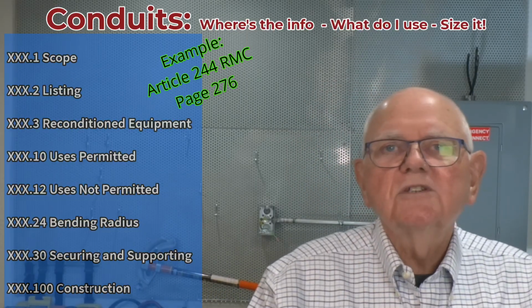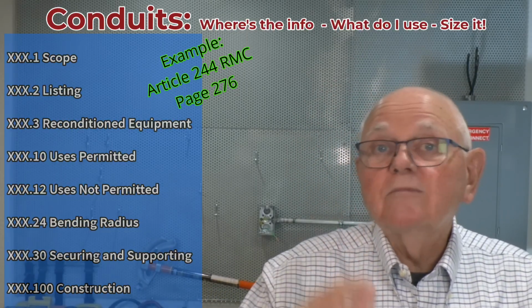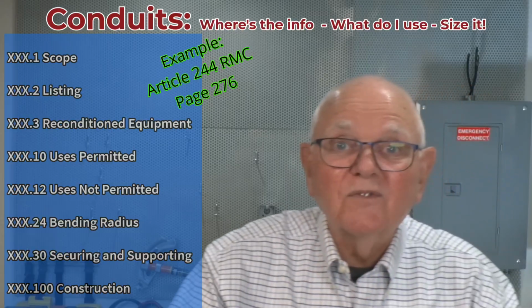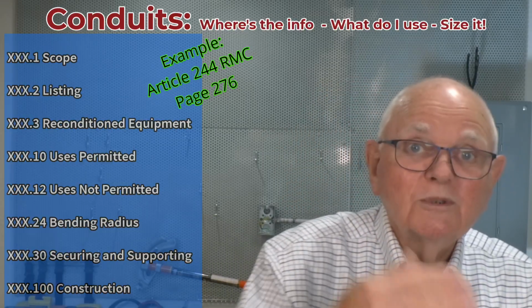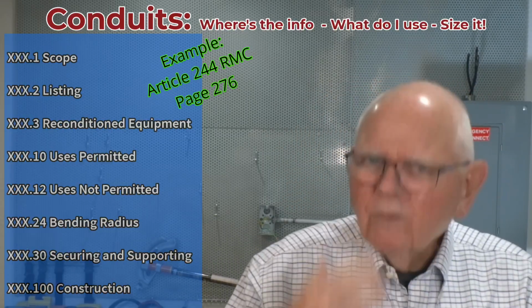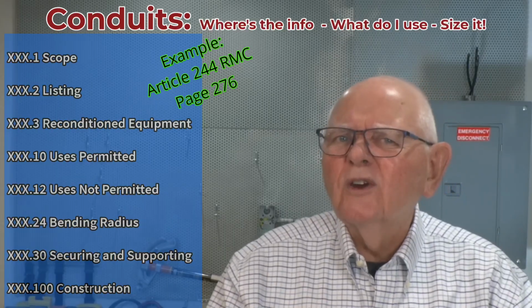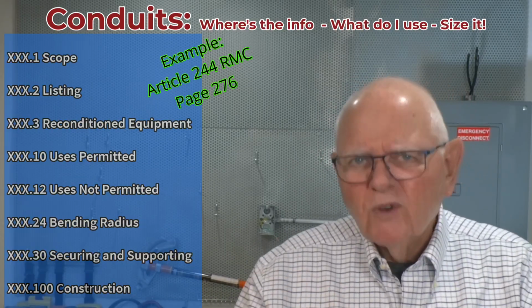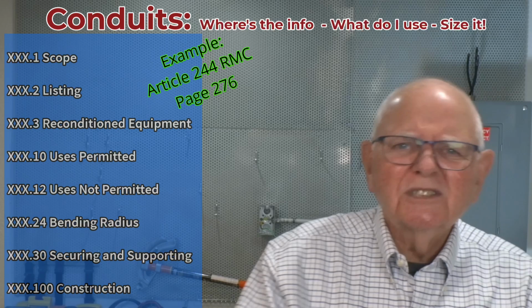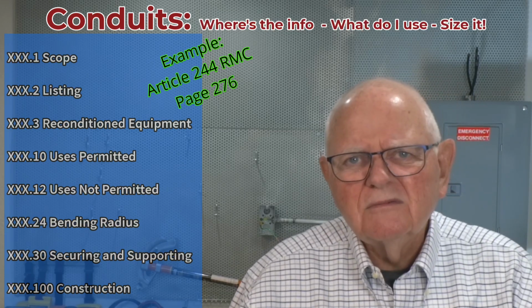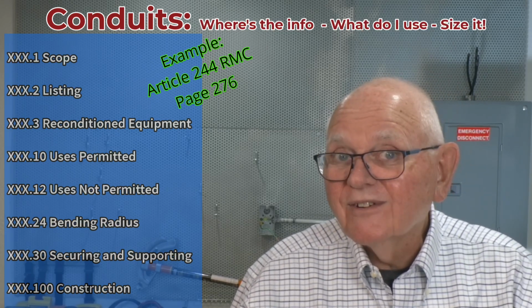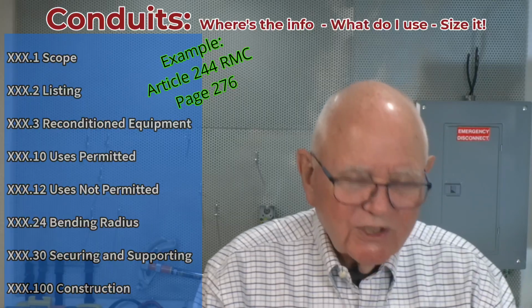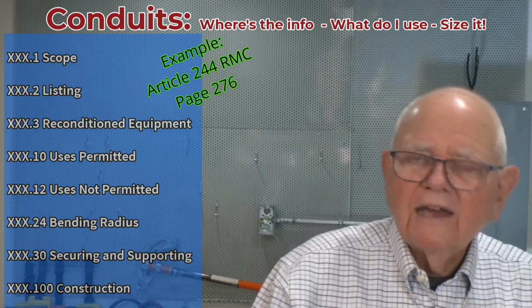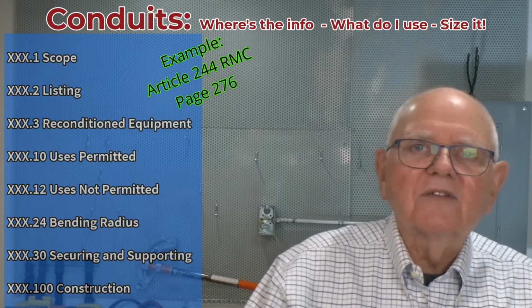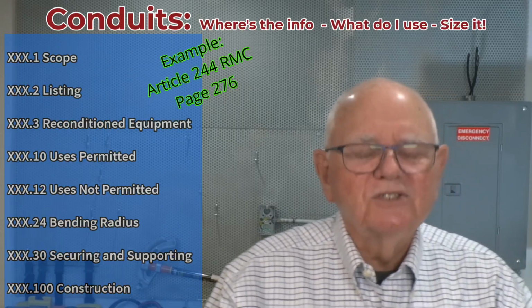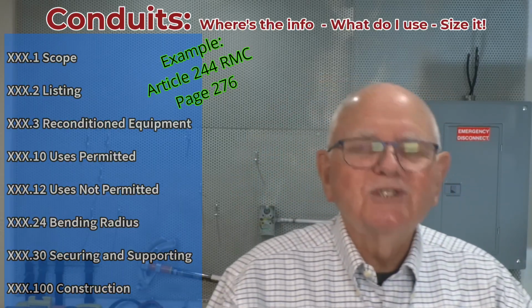If you look at the definition of recondition, it talks about I'm sending something out, typically back to the factory, in order to be refurbished and made like new. When was the last time you sent conduit back to the factory to get refurbished so that it looks just like it was when it was brand new? I don't think I ever have. Okay, I know I never have. So anyway, be aware of that. Yes, I can use a conduit out of the scrap pile if it works or whatever, as long as it's in good shape and so on and so forth. A little common sense there, I think.